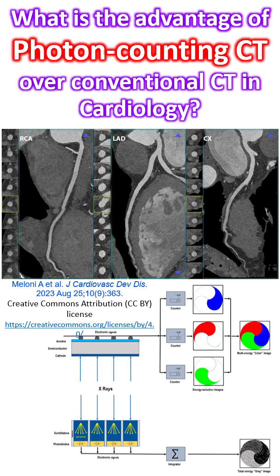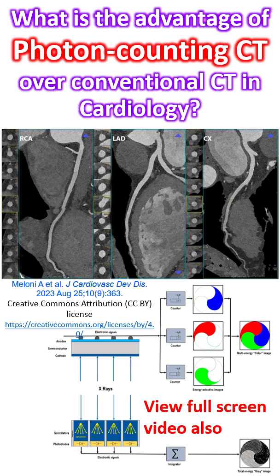Conventional CT uses a two-step indirect conversion process of detection. Photons in the X-ray beam are transformed by a scintillator to visible light. These secondary photons are absorbed by an array of photodiodes and converted to electrical signals. Thus, by integrating the energy of all X-ray photons over a specific time frame, the conventional CT detector loses the ability to retain the energy information of individual X-ray photons.